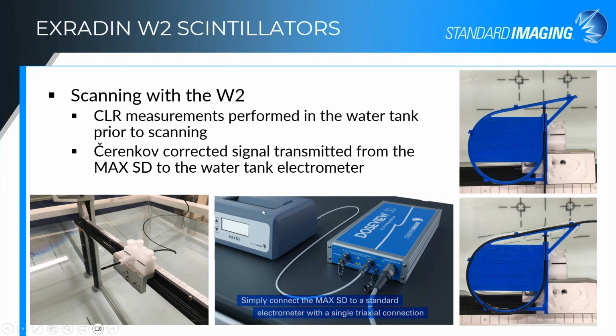You do have to scan slowly with the device because of the timing of that subtraction happening every 10 milliseconds, as well as just the fact that it's a low signal device, and so the scans are going to be quite noisy if you scan at a rapid speed. So we recommend about 1 second measurement per dwell point. Which does add up a little bit, but remember this is small fields only. This isn't really a device that is targeting large fields. This is to get down into those tricky small fields.